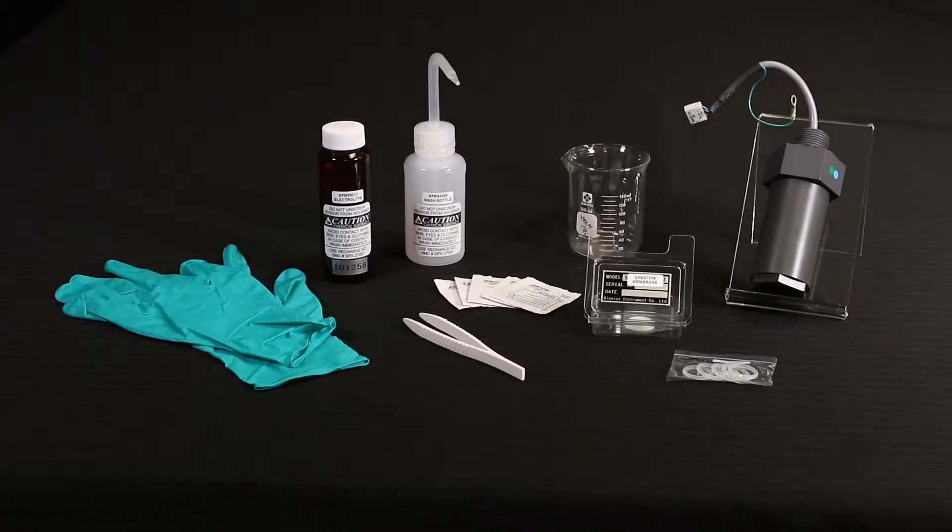Specifically for the ammonia detector, you will have to rebuild the liquid EC cell first. Recharge the sensor cell using the liquid EC cell rebuild process. This includes recharging the electrolyte and rebuilding the electrochemical cell. Please note that the gas detector has been previously removed from service and brought to a clean area for this procedure.